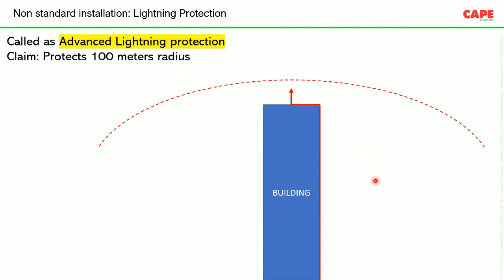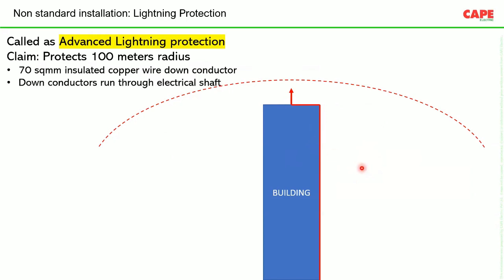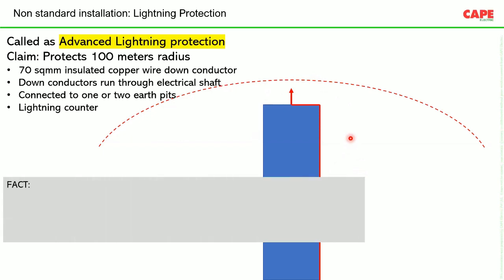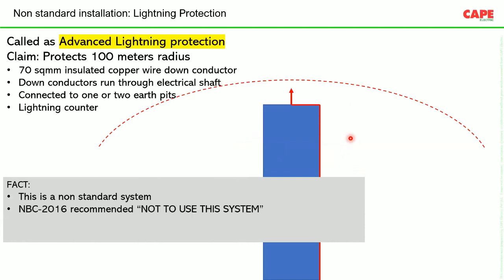So basically, these non-standard systems claim that it protects up to 100-meter radius, and you need to have one down conductor, 70 square millimeters of copper wire, and one earth pit. So basically, one rod, one down conductor, and one earth pit. And this down conductor can be routed anywhere, most often through the electrical shaft. And then the owner of the building believes that he is protecting not only his building, but he is also protecting all his neighbors. The only word to call this is a non-standard system.